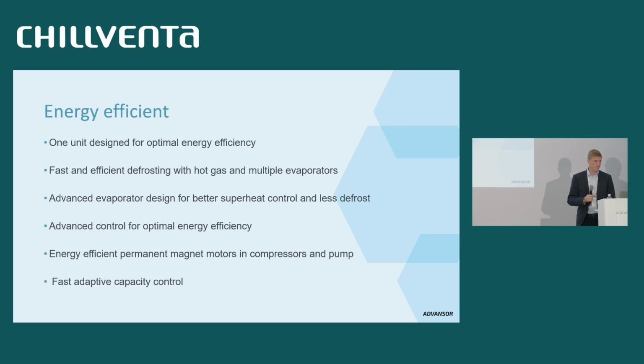Energy efficient. As I said, the overall unit is designed for high energy efficiency. So, for example, on the defrost, we use hot gas to defrost it, but it's not similar to other heat pumps or reversible heat pumps where we have a four-way valve changing the direction of the refrigerant. Here our evaporators are split in multiple circuits or coils, so we can take out part of the evaporators, defrost it, while we keep operating on the rest of them, so we can still provide heating for the building at the same time as we defrost the coils or the evaporators.